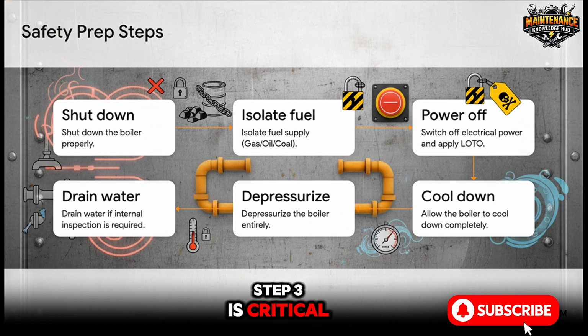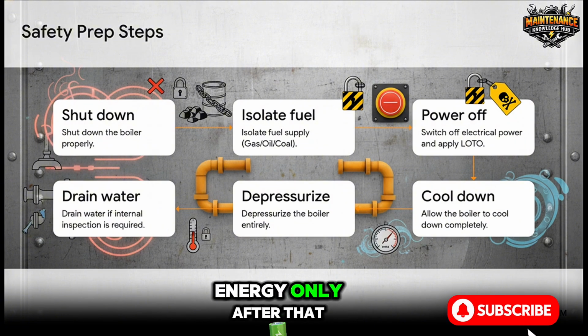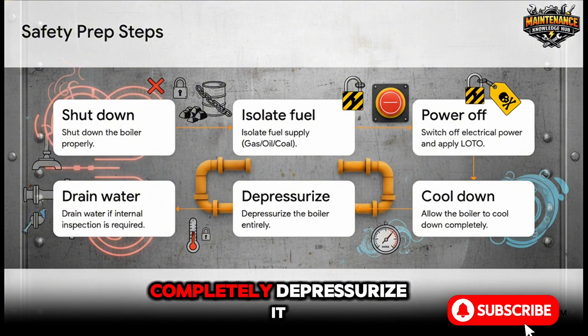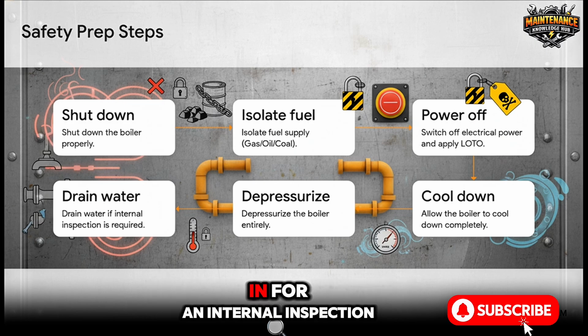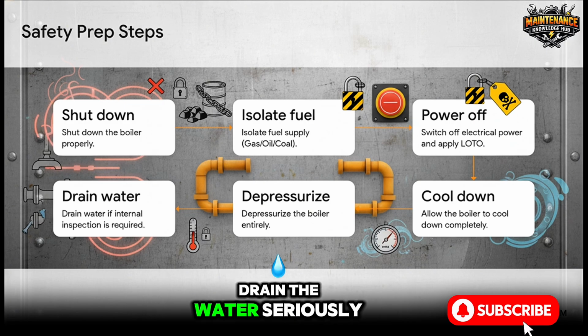Now, step 3 is critical. Switch off the electrical power and apply lockout/tagout, or LOTO. You are securing the energy. Only after that do you let the boiler cool down, completely depressurize it, and if you're going in for an internal inspection, drain the water. Seriously, this sequence is your lifeline.